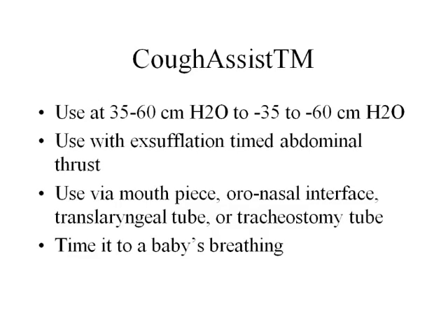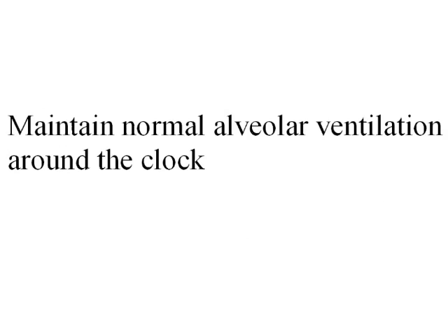One of the most common mistakes is to use the cough assist at grossly ineffective pressures. The pressures must be 40 or more in general. And also, you must apply an abdominal thrust during the negative pressure. Otherwise, it either won't work at all or it'll work very little. Very few people understand this, but that's the way it is. Very few doctors understand that.